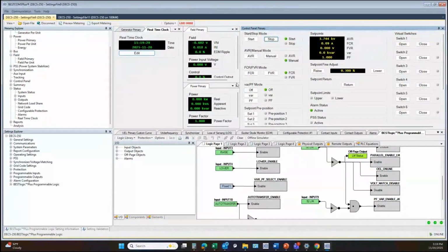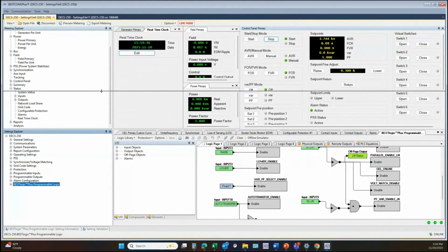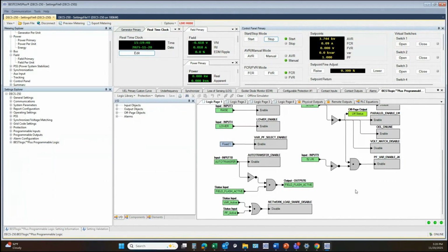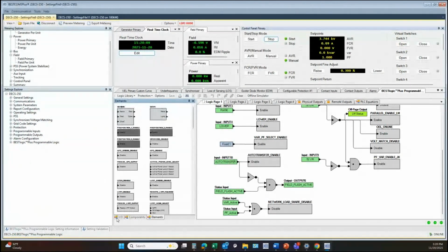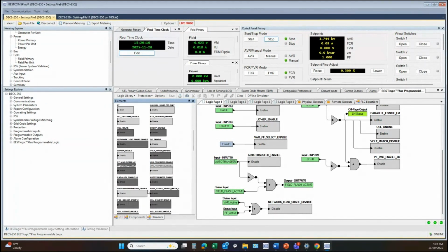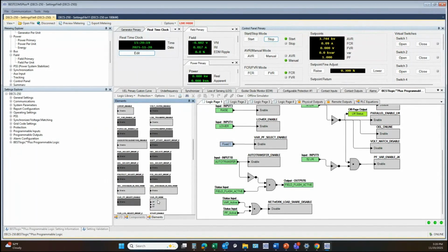So again, that becomes important to make sure you're setting this VAR power factor mode selection up properly. If you don't want to have to deal with that in the control panel every time, then you can set up logic to do it. The logic is very simple, drag and drop. So we will go through real quickly setting up that logic to say we want to go into power factor whenever this logic becomes enabled. We always want to be in power factor control. So to set that logic up, we have 3 tabs to choose from down here, and the elements tab is where we'll find that var power factor mode logic element.